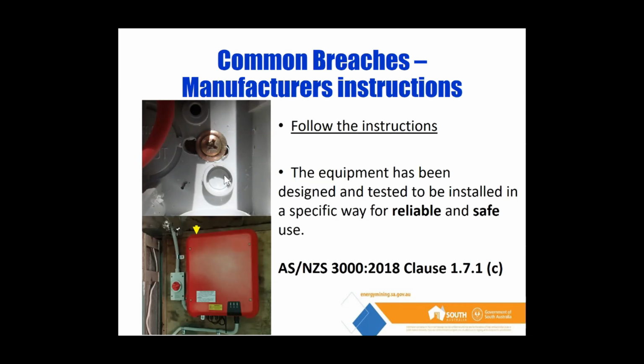So really we would fire that as a breach. And then the second photo there is just a solar inverter. And this was actually about 6 meters high up on a shed wall. It was about a 23 or 24 degree day. I remember it was a beautiful day. But once I was up the top on a mezzanine floor, it was sweltering up there. Now this inverter was switching on and off constantly because it was going into overtemp. And in the manufacturer's installation manual, it actually gives specific clearances for the inverter. And right here, we're hard up against the isolator. And it was very hot there, and it's obviously not going to function as intended. So 3000, clause 171C, talks about the manufacturer's instructions when installing products.